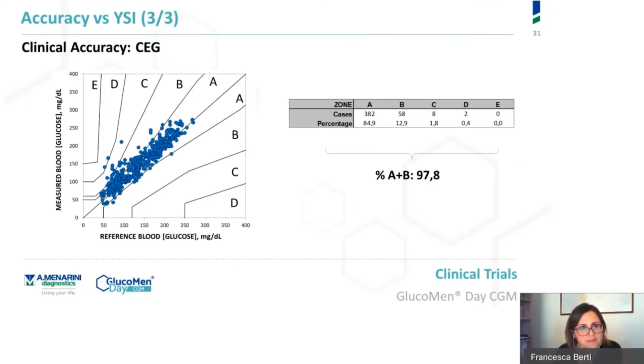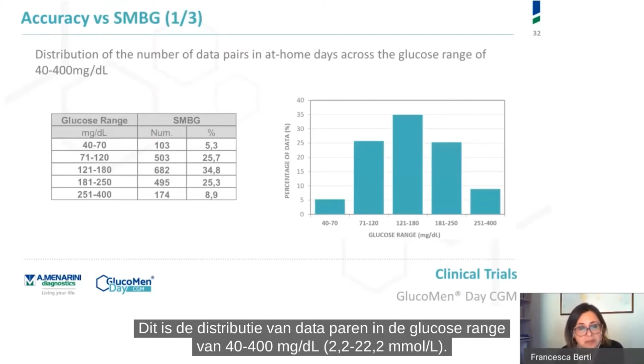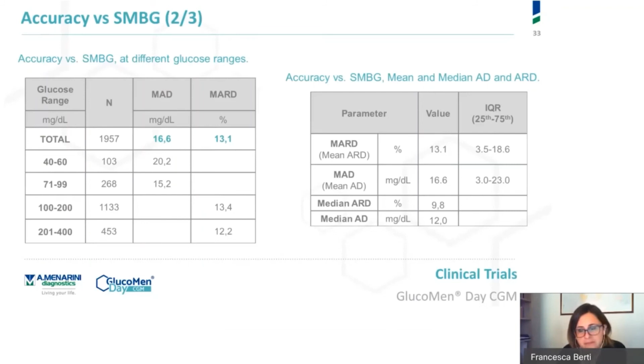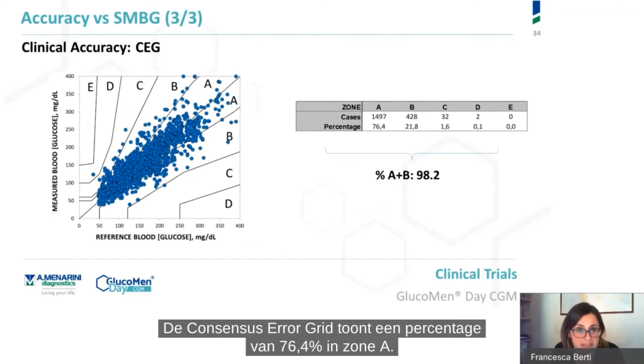These are the results of accuracy versus SMBG obtained during the at-home monitoring period. This is the distribution of data pairs over the glucose range between 40 and 400 milligram per deciliter. The accuracy assessment shows that an MARD of 13.1% was obtained and an MAD of 16.6 milligram per deciliter. Also here we can see a breakdown of the results of MAD and MARD in the most relevant glucose intervals. The consensus error grid analysis shows that 76.4% of the data fall in zone A, and that 98.2% of data fall in zones A and B combined together.